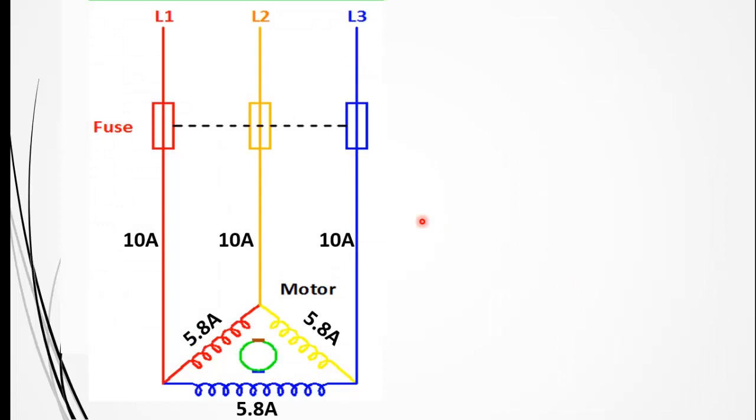First, I will explain what happens when single phasing occurs on a three-phase motor. Here you can see that during normal operation, all phases are carrying equal current. Since the motor is connected in the delta formation, the line currents are 10 amperes whereas the phase currents are 5.8 amperes. To see the relation between line and phase currents in delta and star networks, you can watch my video—the link appears on the top right side of your screen.